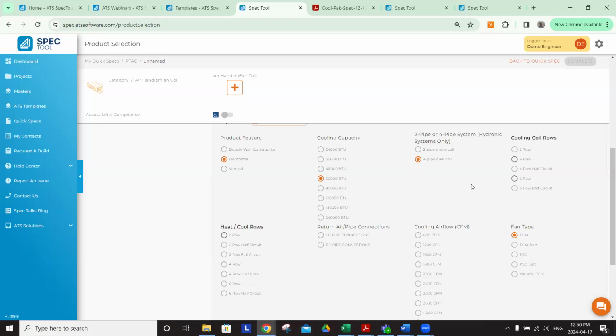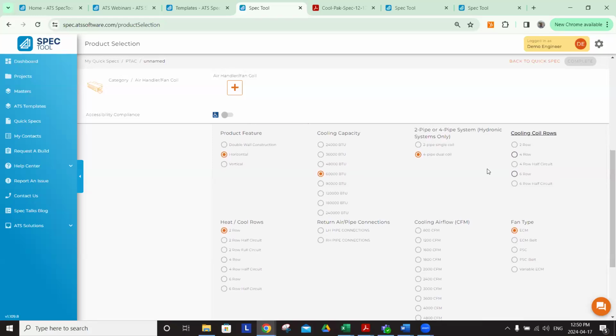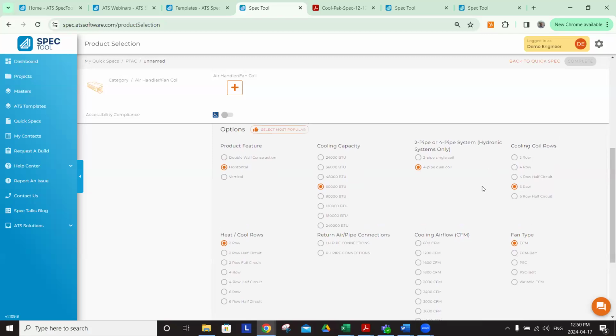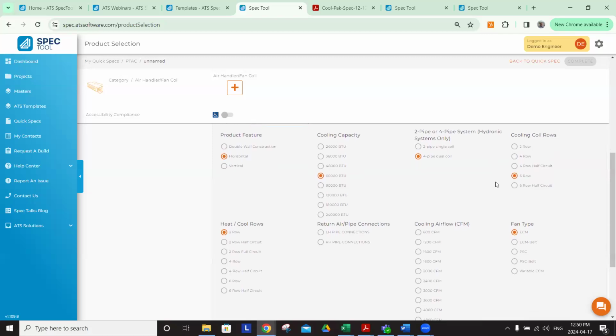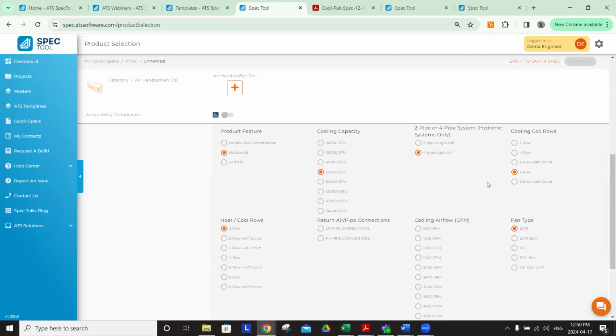So now the only selections left are heating and cooling rows. Now, if it's a 2-pipe unit, the heat cool rows would be the same for heating or cooling. Since we've chosen 4-pipe, we have to make 1 selection for heating and 1 selection for cooling. Now, this is where we need to take it another step, right? We need to dig a little deeper in here. What I'm going to recommend is that if you're specifying a unit of this type, you choose the largest available option, because that's going to trigger us to look at it, and if we were to quote it, we're going to quote the more expensive unit, and that's going to build us in some protection.